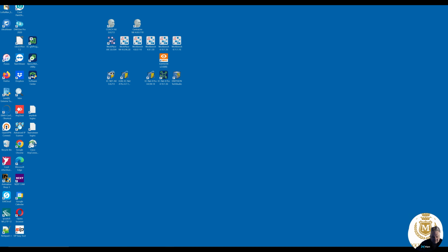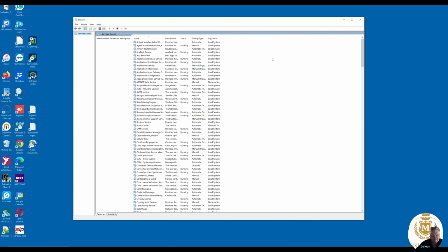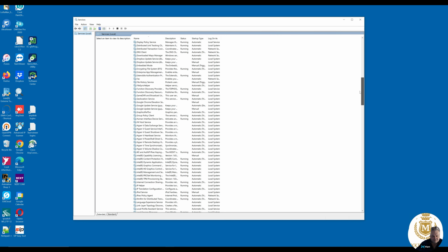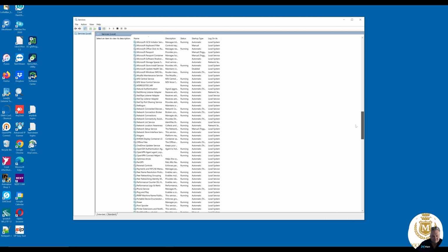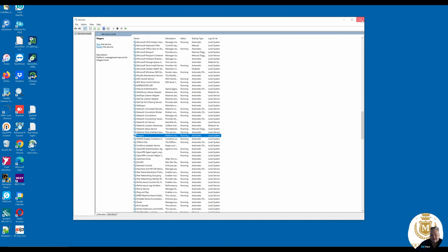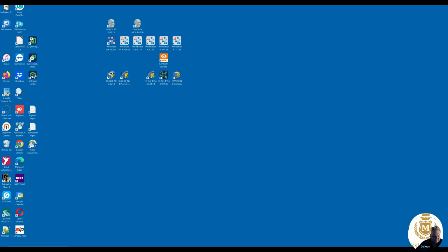If I go to my services and look for Niagara, which is there, you will see this saying 4.8. There you go, Niagara 4.8. Well, that's no good to me. I'm using 4.11 software, so I need to have my platform as 4.11. So that's good, it's happened. At least you can see the issues there.